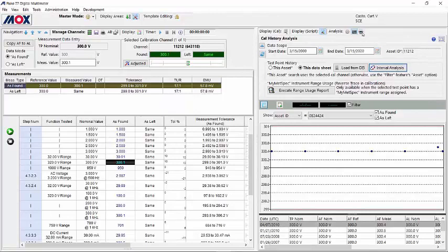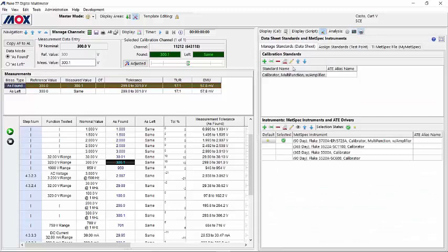All right. And then, of course, our last tool in calibration mode is the calibration standard setup. Now, this requires a configuration option to enable in calibration mode. A lot of labs don't want technicians changing the standards configurations during the calibration. Some labs might. That's really up to you. We'll be talking about this form in great detail later, so I really won't say anything else about it right now. Okay, that's primarily all you need to know for now about calibration. As I said, all of the other functionality of performing calibrations and loading data sheets to do cals and all that we'll talk about later.